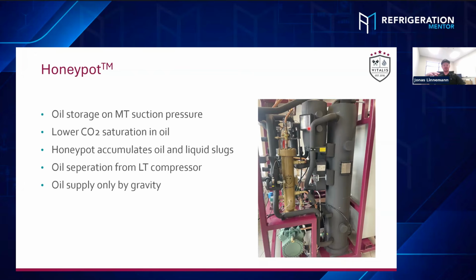So we basically store the oil inside a suction accumulator vessel on MT suction pressure, which is the lowest possible pressure for the oil. And we just feed that back through that little hose to the distribution block by gravity into the medium temp compressors because there's no major pressure difference. We use the height difference to refill that oil. And by not causing a pressure loss while refilling, there's absolutely no foam inside the oil. So that's the best condition you could provide to the compressor.